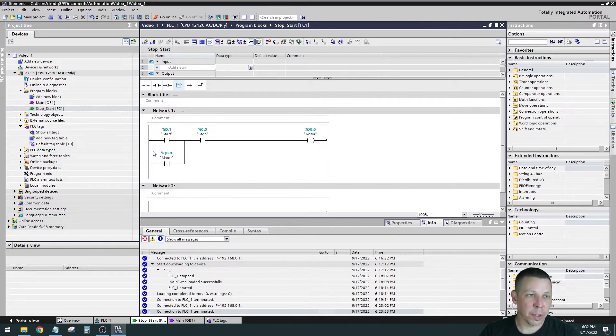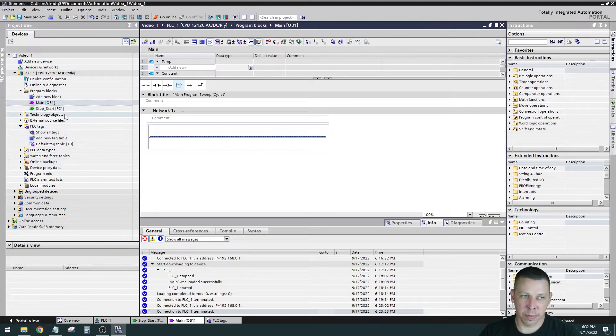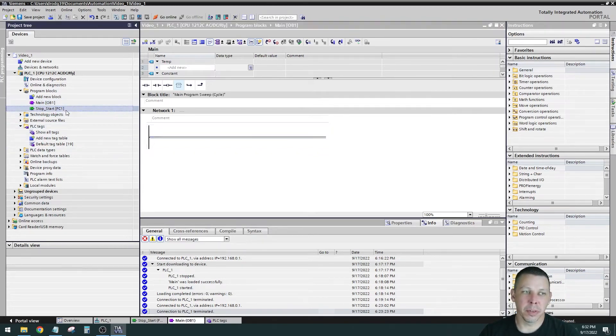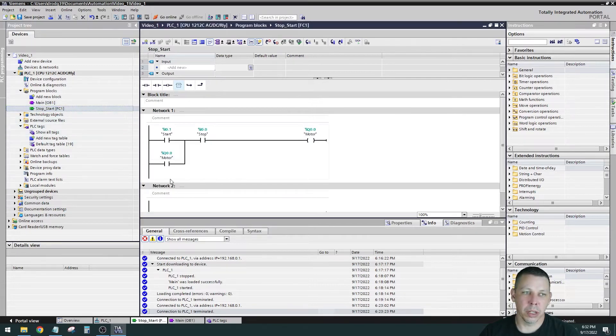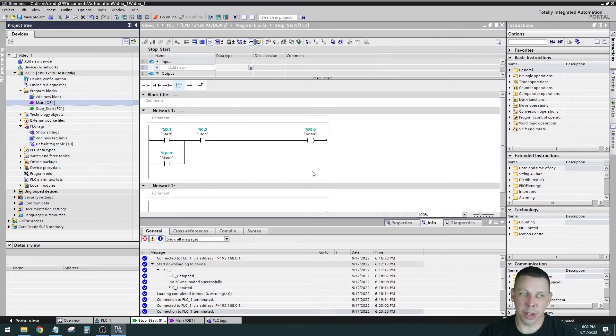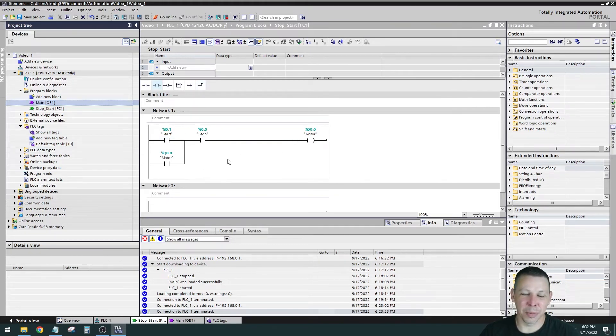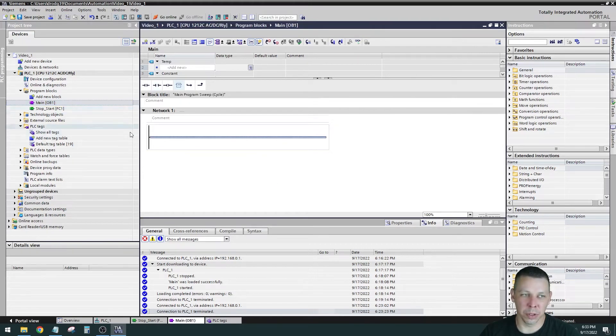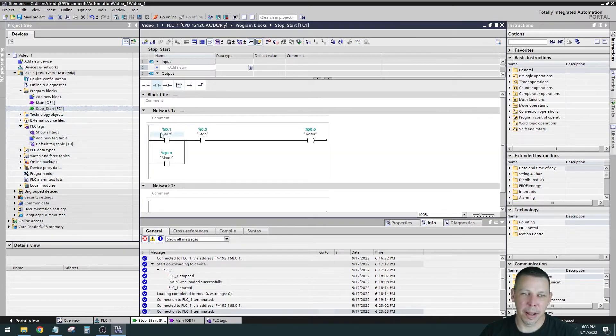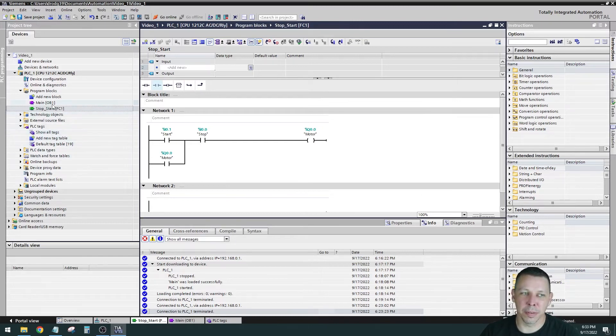Before we get to that — remember OB1 was blank before? OB1 is the only thing called when the processor turns on. Even though we have logic in FC1, if you download the program the processor won't give faults or warnings, but when you put it in run mode the logic won't execute. The processor goes to OB1, sees nothing there, and nothing happens. You will do this — you'll add a function and forget to add it to OB1, or forget to update OB1 after editing.